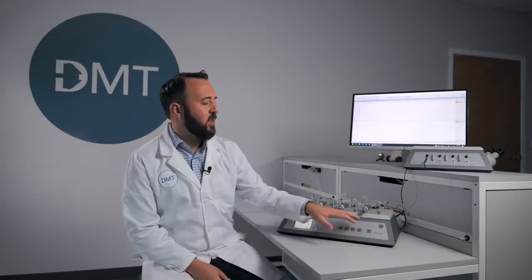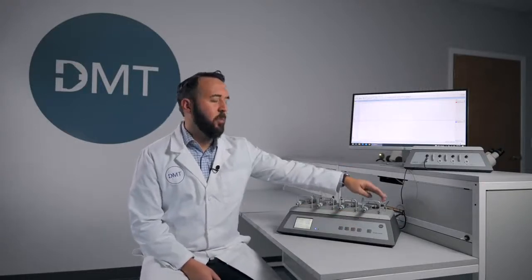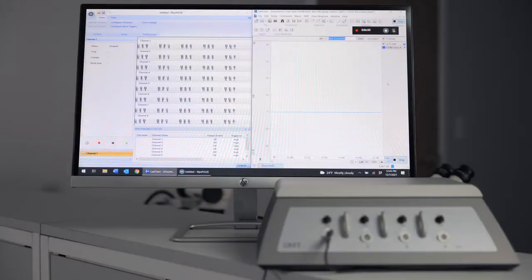After you have mounted your tissue, you can bring the chamber back to the interface, plug it in, and start bubbling. You can start LabChart during the 10-minute rest period. After 10 minutes have passed, you need to find the optimal voltage for your tissue. You should place 1 millinewton of tension on the strip.